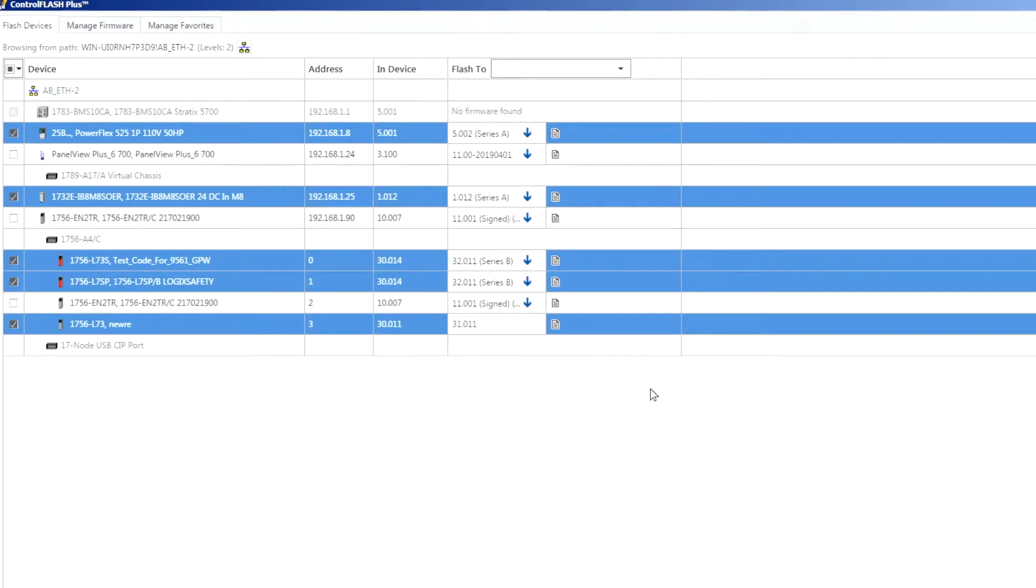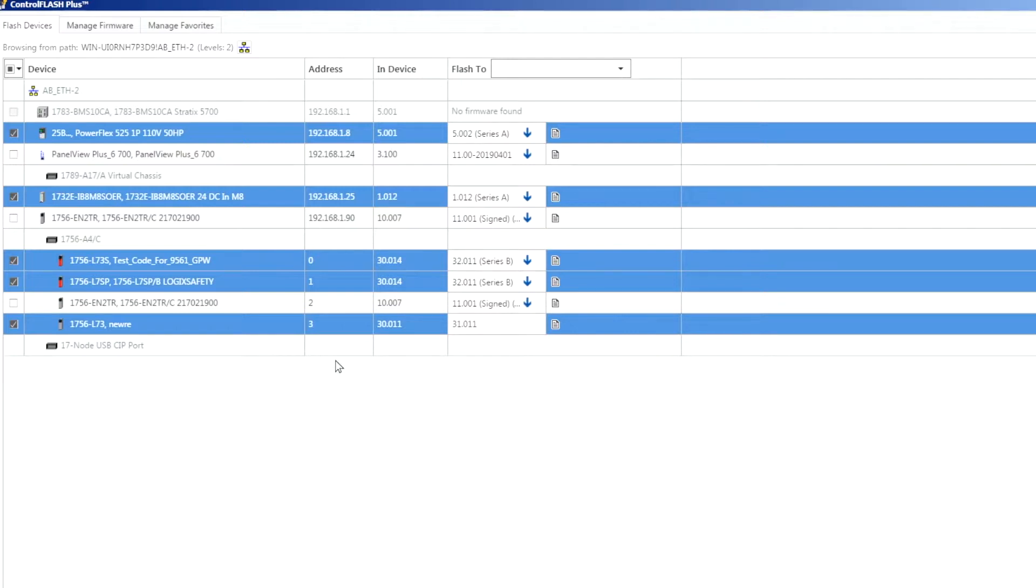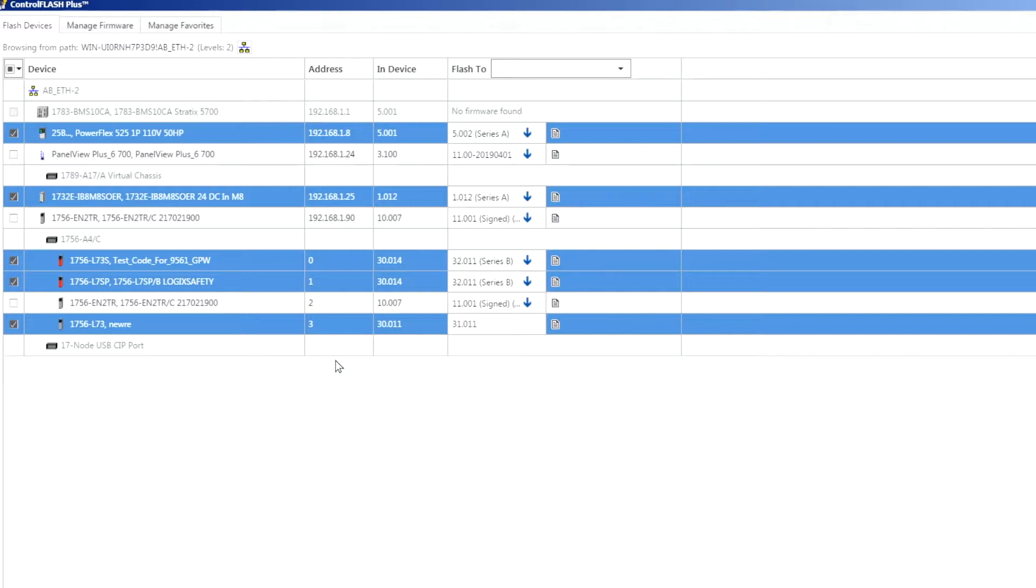The real power of ControlFlash Plus comes from the ability to create a flash list and then flash multiple devices concurrently. This is going to depend on your network topology. If you're using a star network it can flash 20 devices at a time concurrently. If you're using a device level ring or linear topology it's going to identify that topology and then go through and flash each one of those devices one at a time so that it doesn't break the ring.